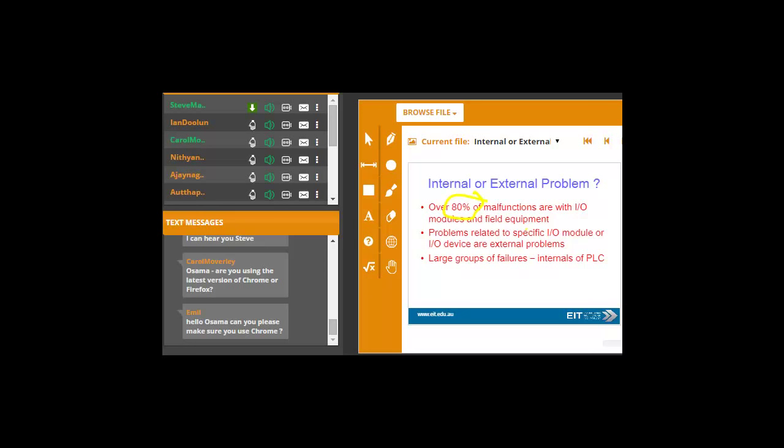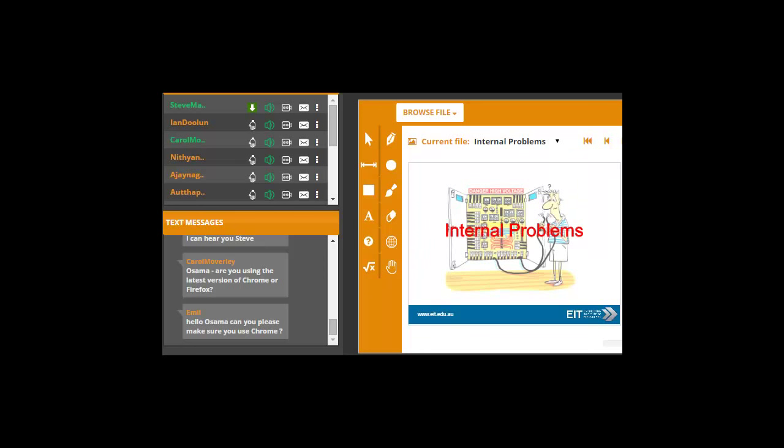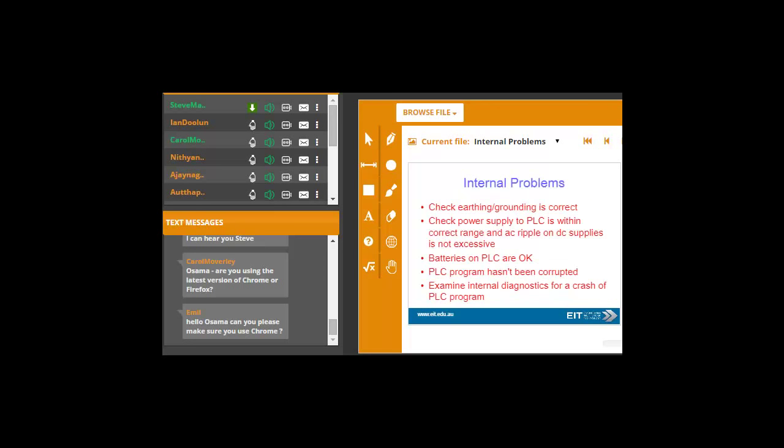So whenever you walk to a PLC and someone says there's a problem, always assume until you've proven wrong that it's something to do with the field wiring or the outputs. Something has gone wrong there. And let's face it, PLCs are often in a nice, clean environment. But the field wiring is often in a filthy, industrial, horrible environment. So really, the problems generally relate to the I/O modules. Sometimes, occasionally, you'll find that I/O modules failed and you'll lose 16 inputs, for example. And I'll come back to that point, but that's very unlikely. If you do see large groups of failures, for example, you see eight inputs suddenly disappeared or it shows that there's an open circuit condition, you'll often find it's due to a input card that has failed. But that's very unusual. But sometimes you can get a problem, for example, overheating of an input card due to the environment. And you could get an issue there.